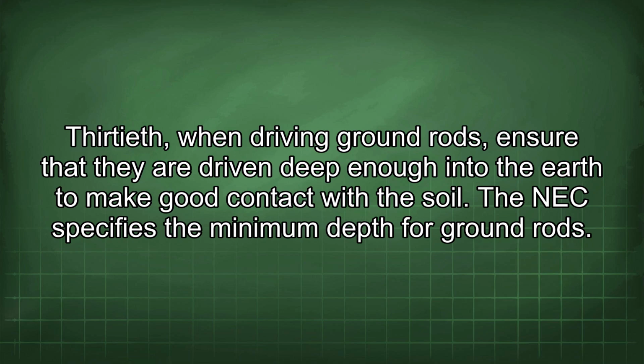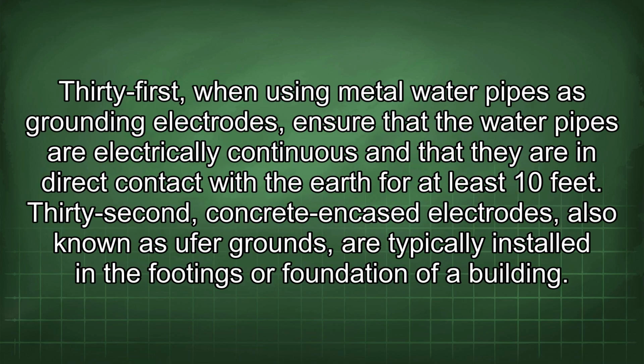30th. When driving ground rods, ensure that they are driven deep enough into the earth to make good contact with the soil. The NEC specifies the minimum depth for ground rods. 31st. When using metal water pipes as grounding electrodes, ensure that the water pipes are electrically continuous and that they are in direct contact with the earth for at least 10 feet.